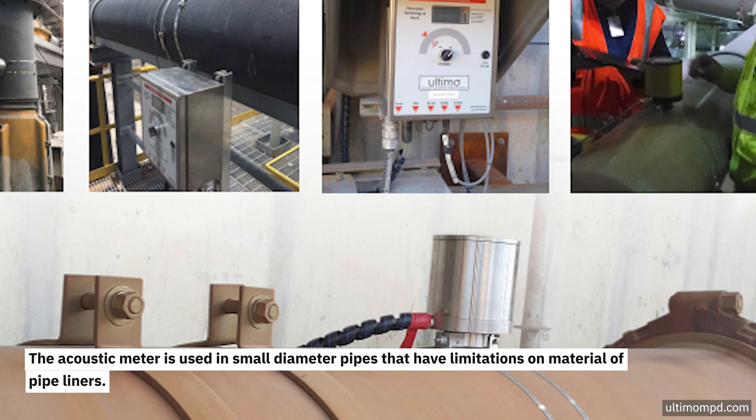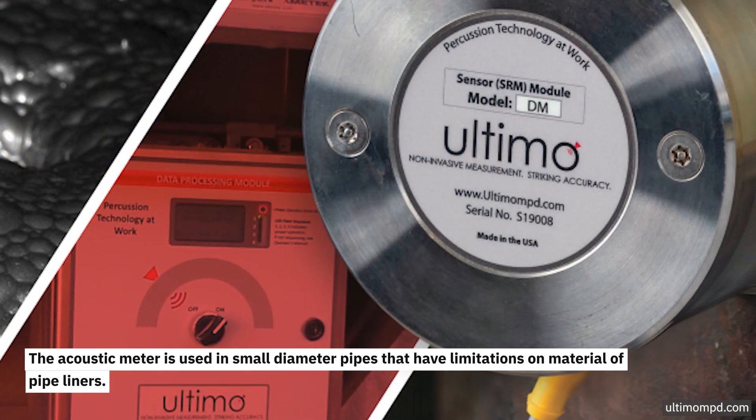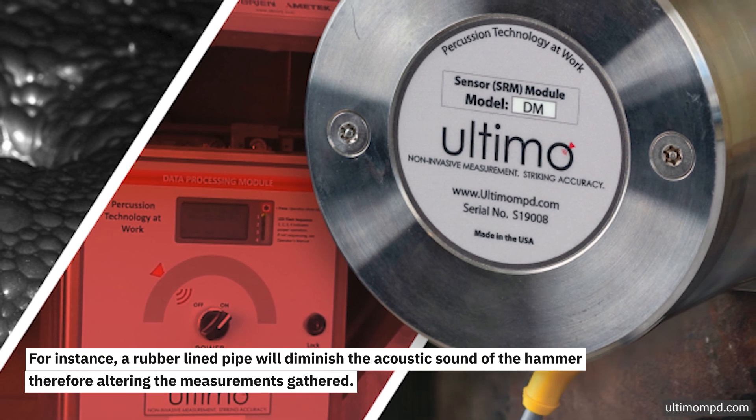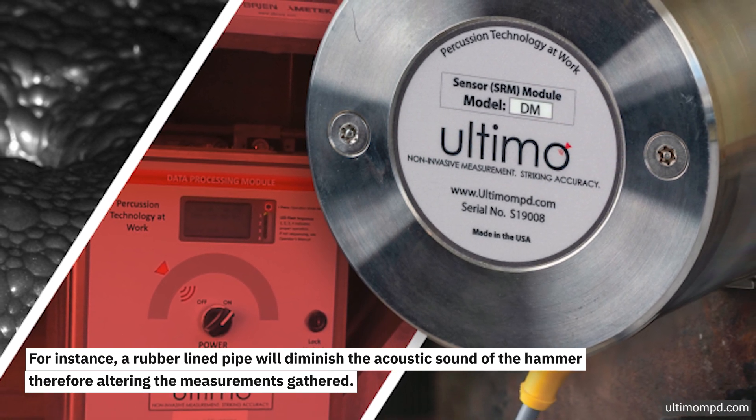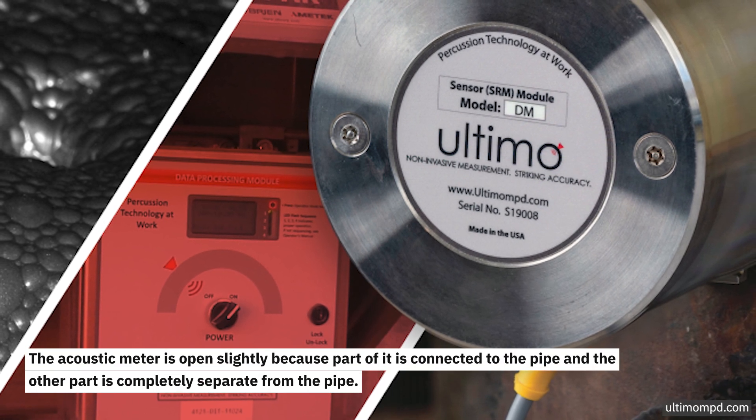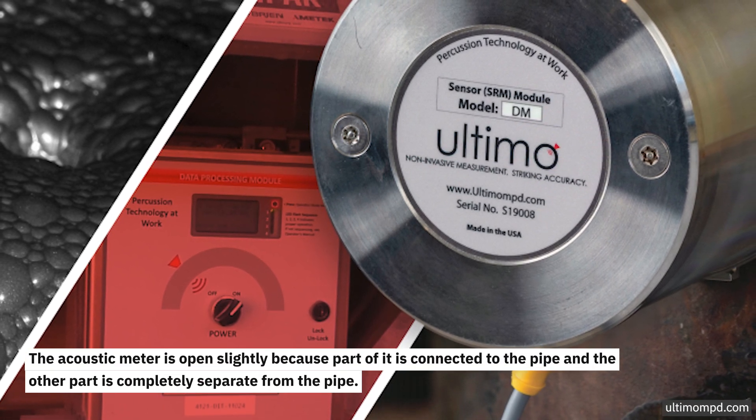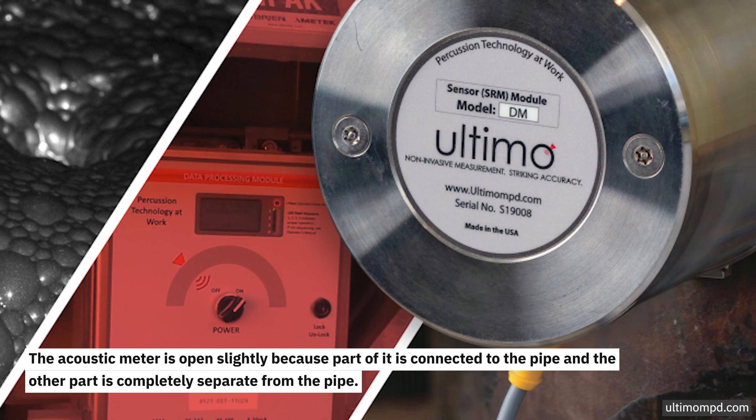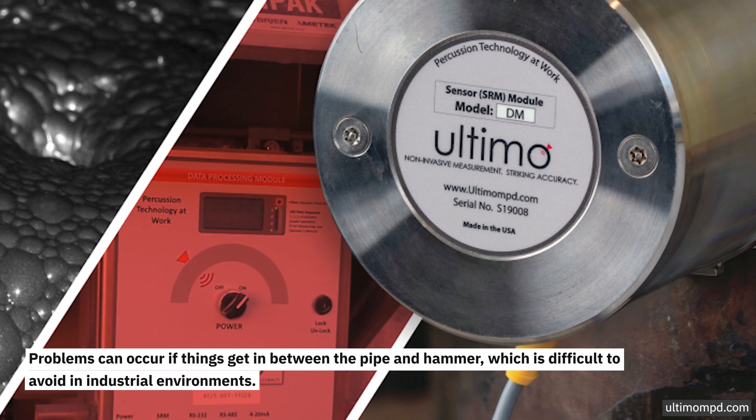The acoustic meter is used in small diameter pipes that have limitations on materials of pipe liners. For instance, a rubber lined pipe will diminish the acoustic sound of the hammer, therefore altering the measurements gathered. The acoustic meter is open slightly because part of it is connected to the pipe and the other part is completely separate from the pipe. Problems can occur if material gets in between the pipe and hammer, which is difficult to avoid in industrial environments.